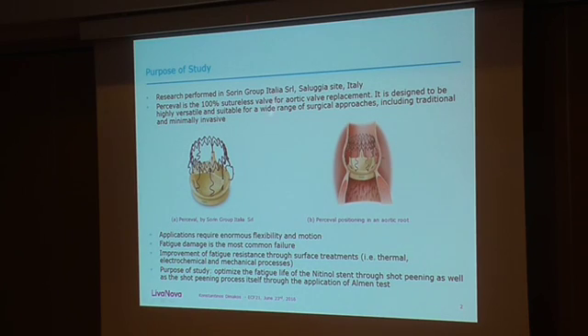You can understand there's some fatigue that this component is subjected to, as well as the blood vessels when they're expanding and contracting. They also tend to reduce the fatigue life of this component. This part here is the nitinol stent. And so there have been many studies to improve this component through various surface treatments. Thermal, electrochemical, and mechanical processes.